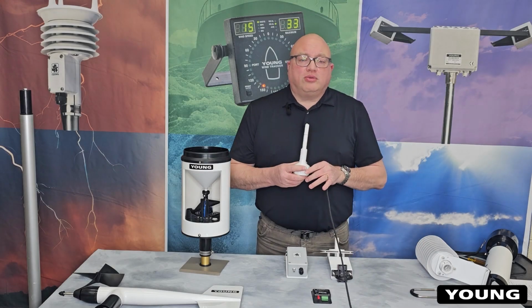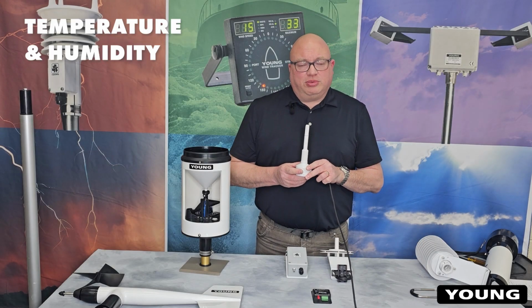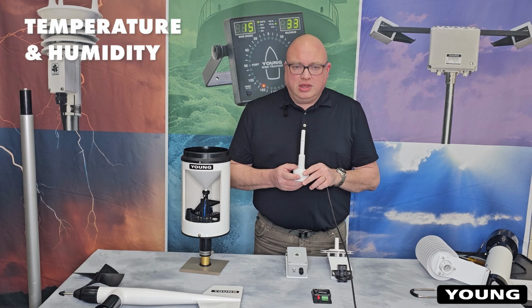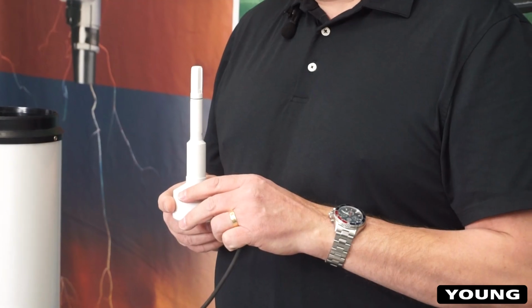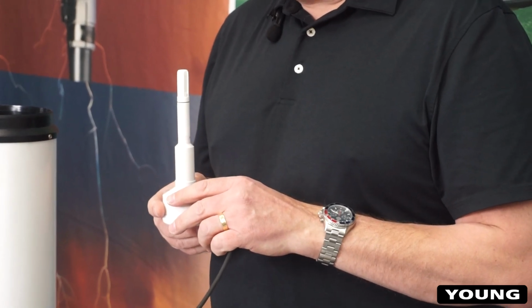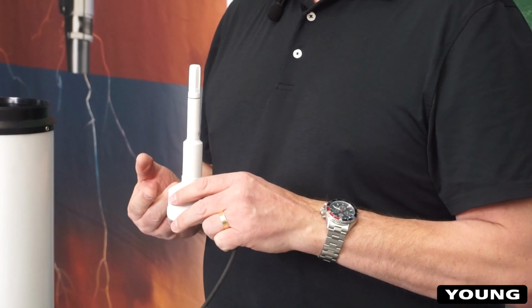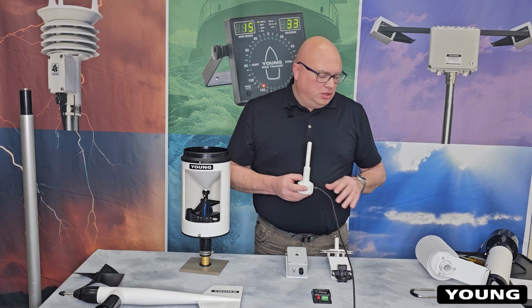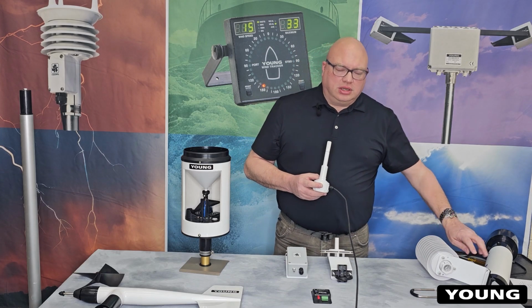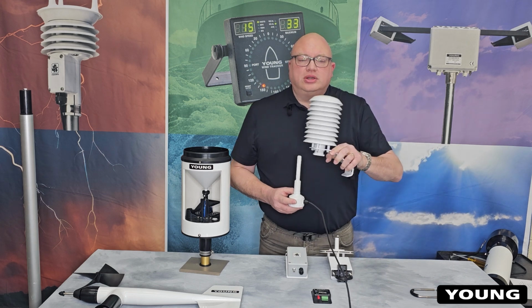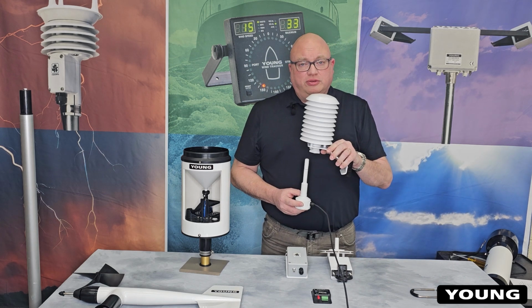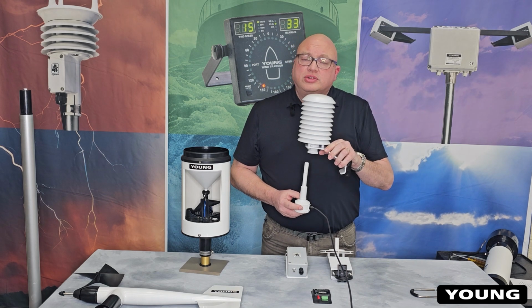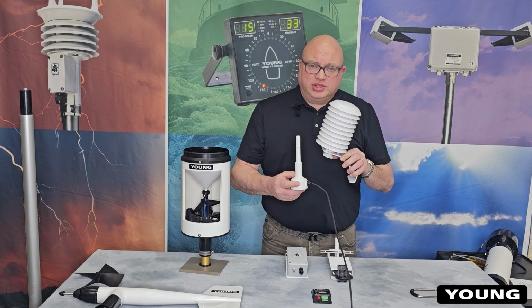Our model 41382 temperature and relative humidity probe. This probe uses a thermistor for measuring temperature and a capacitive element that's used to measure the humidity. We recommend you pair it with a radiation shield, such as our 41003P-24 solar radiation shield that is designed specifically for use with this sensor.